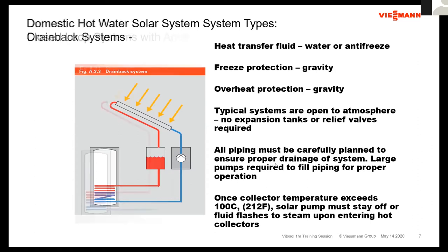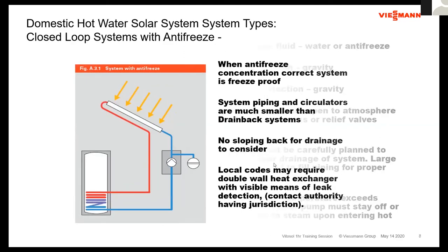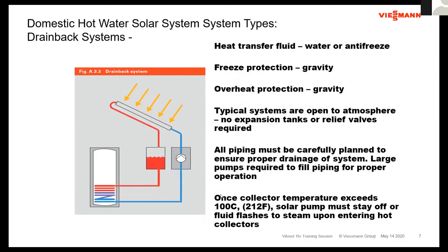Obviously, the piping I just talked about has to be pretty careful. And also special control, typically, to make sure that, you know, this collector is still gathering energy here, but all of a sudden the tank temperature drops where we can turn this pump back on. We have to be very careful that if we push this fluid now into that hot collector, we can start getting some steam hammering, because now that's going to hit that hot surface and we're going to flash that to steam. When water flashes to steam, it expands 1500 times. It makes a bit of a racket. If you ever heard it, you know what I'm talking about. And we want to avoid that from occurring.